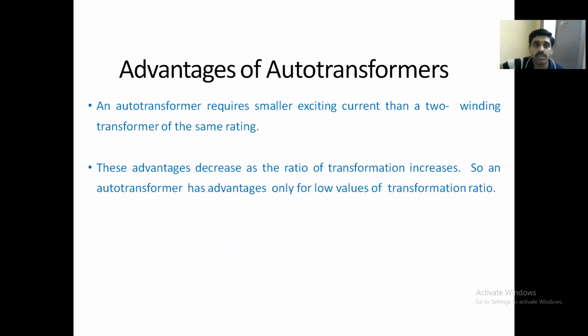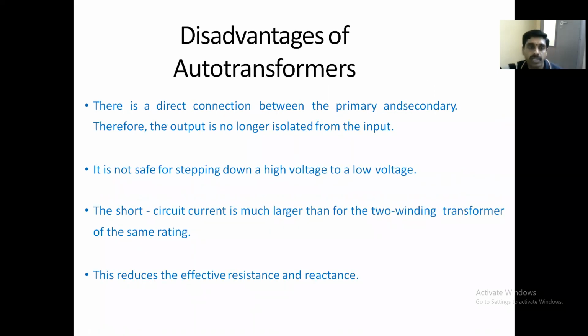You will see the limitations also. An auto transformer requires a smaller exciting current to produce the same flux than a two-winding transformer of the same rating, because the two windings are connected conductively. That's why the flux can be easily linked. Therefore, the exciting current will be less compared to a normal two-winding transformer. These advantages decrease if the transformation ratio increases. So the auto transformer has advantages only for low values of the transformation ratio. So what are the disadvantages of auto transformers?